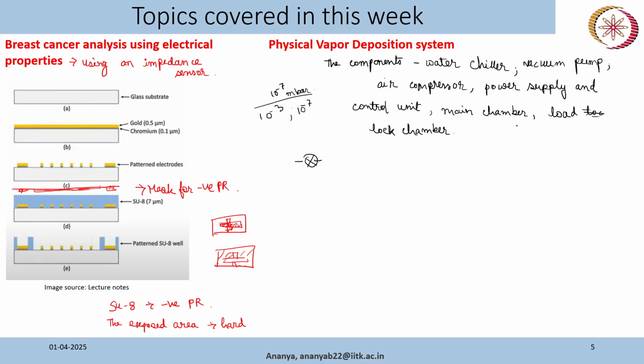In many systems we don't open our main chamber directly, because the pressure inside during deposition, or initially when we are operating, will be very low, say 10 to the power minus 7 millibar. We cannot directly open the chamber; we have to vent it slowly, and we don't normally want to vent it from a very good vacuum. The reason is that after we keep our sample inside the chamber and load our target, it will take a lot of time to create this high vacuum. So there will be one load lock chamber connected to it.